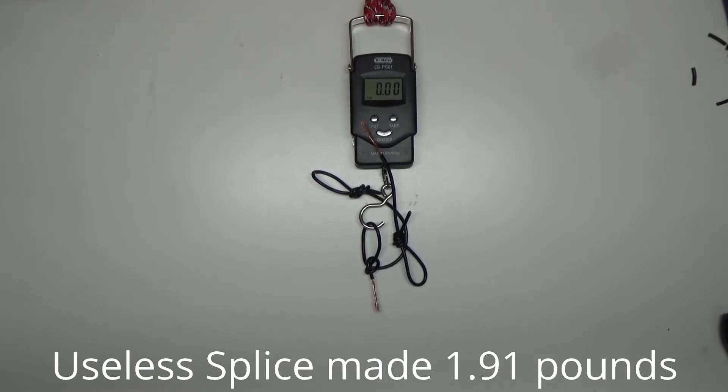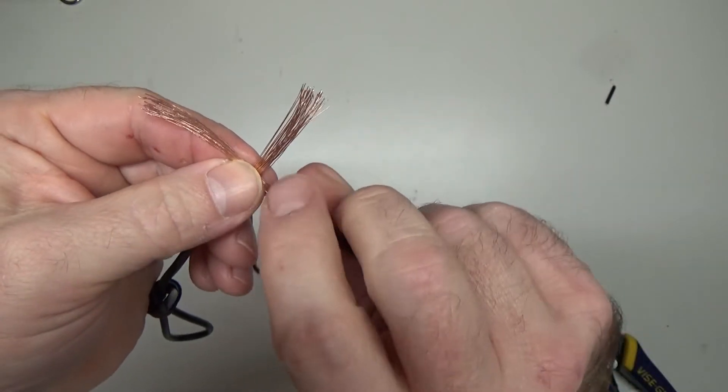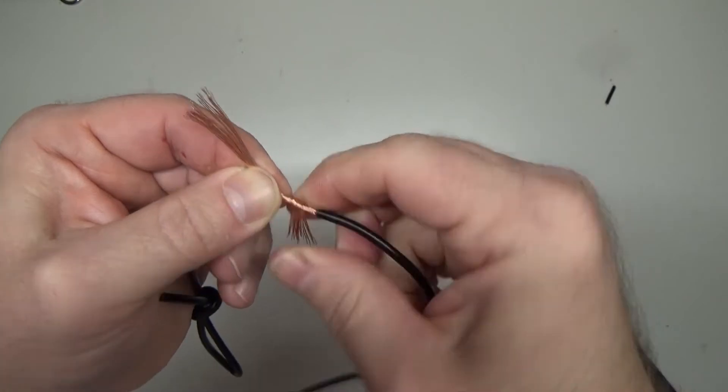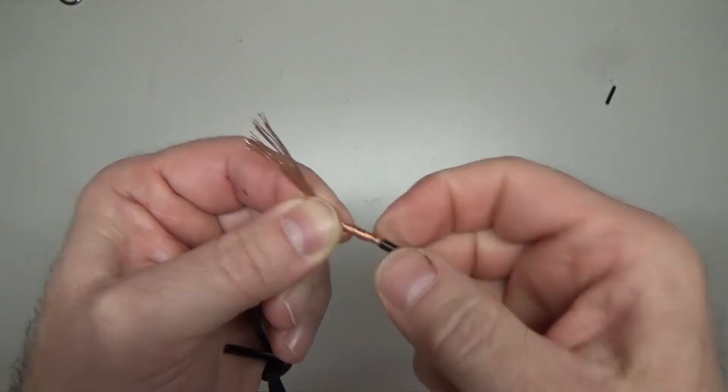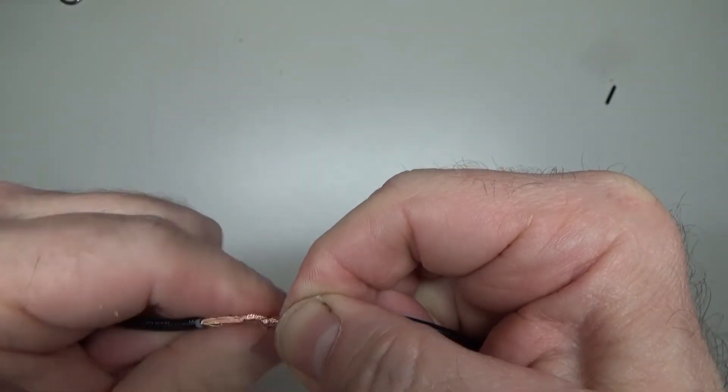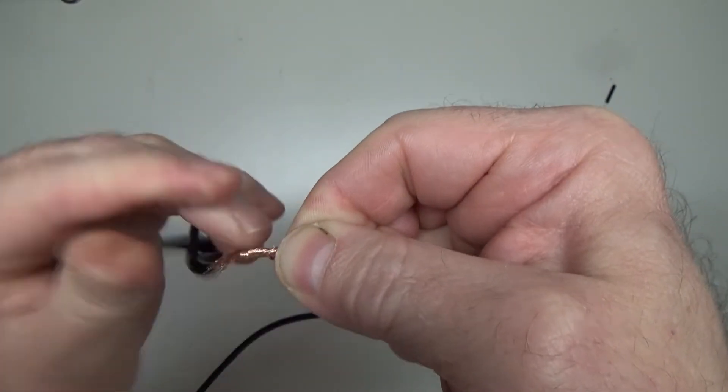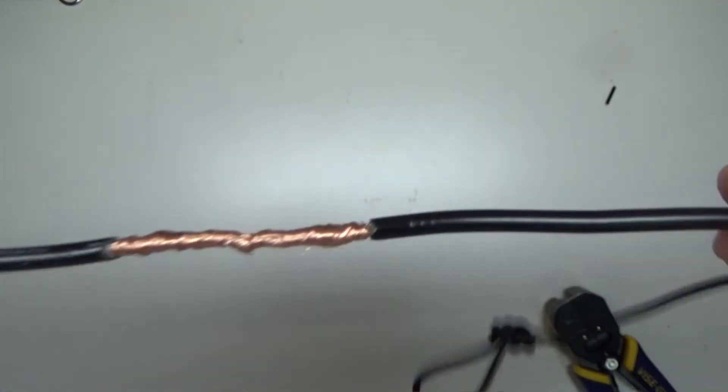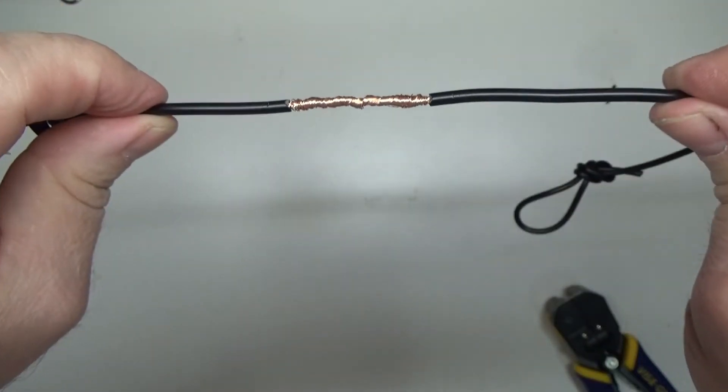Now this time we're going to do the Western Union splice. Cross your wires at the middle of the copper, take this one, wrap it like this, and pull tight on your wire as you wrap it. You start at the middle because it ends your wrap right there at the insulation. Now do this with the opposite direction. This is a pretty stout little wrap right here. There you go, you can see how nice tight package that is. If you want to solder that, you'd have a super strong joint because obviously it would make it all one solid piece.